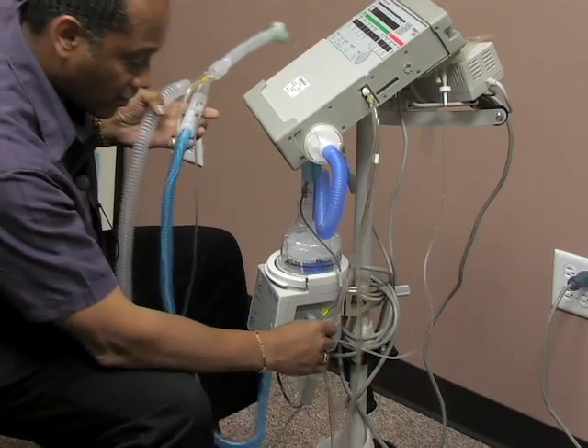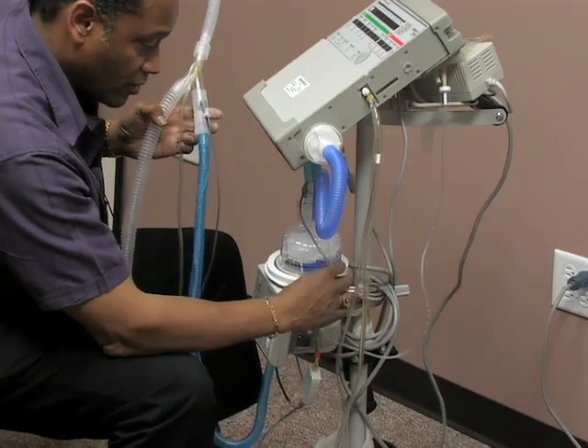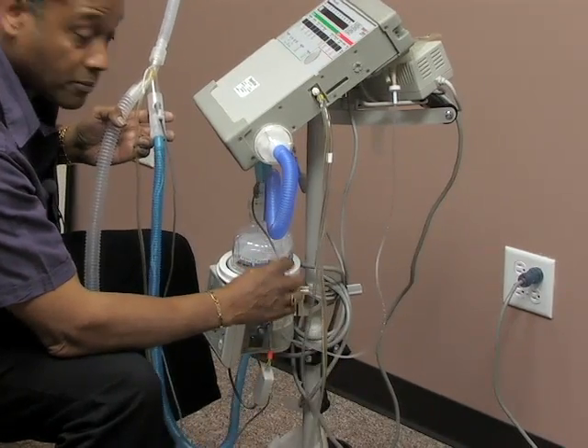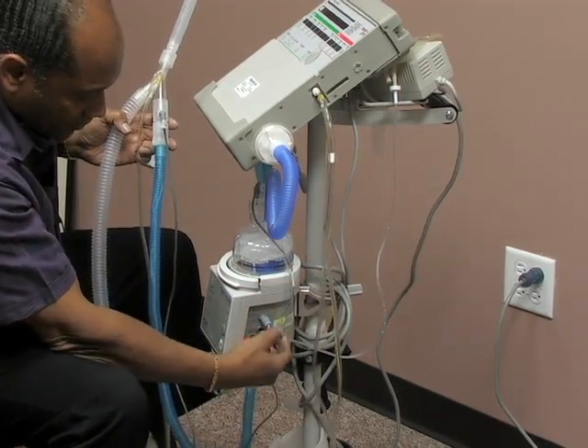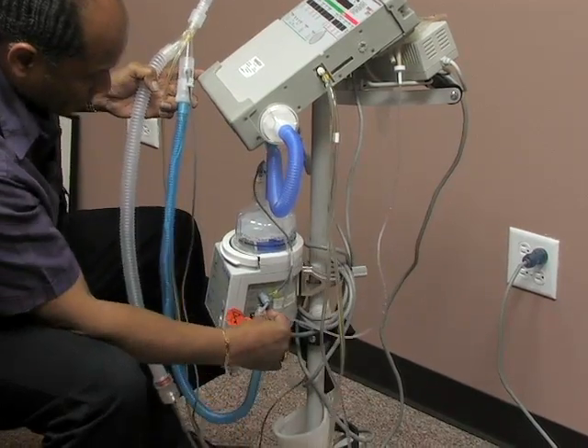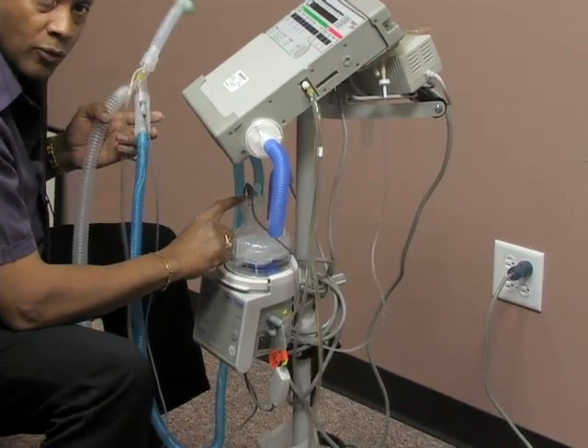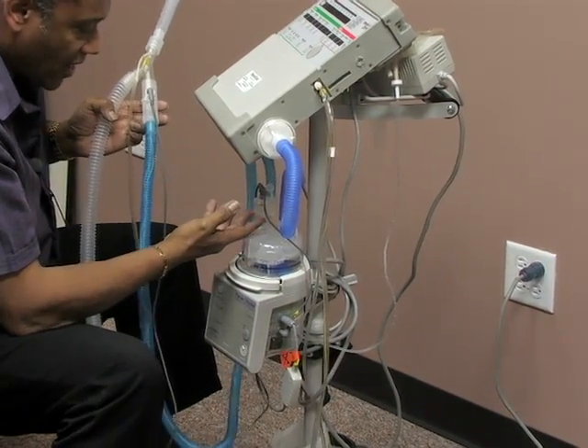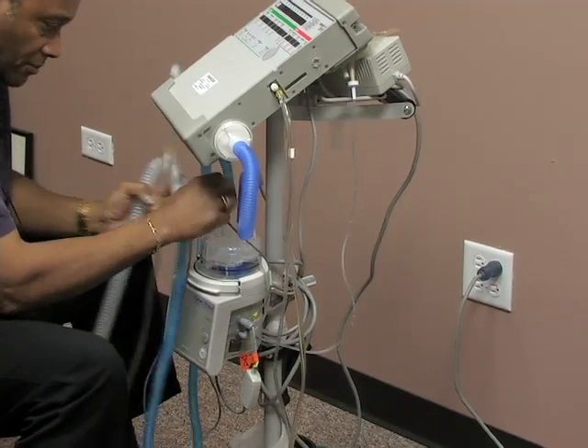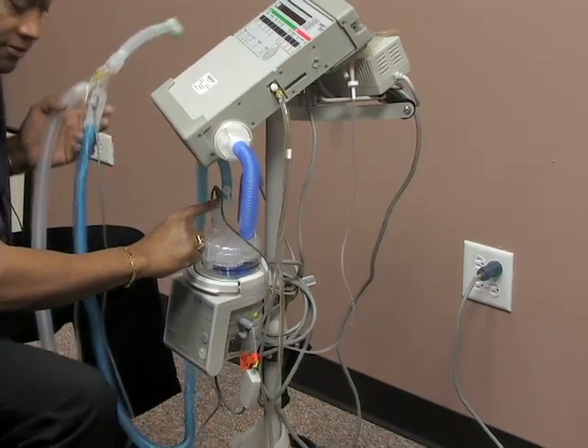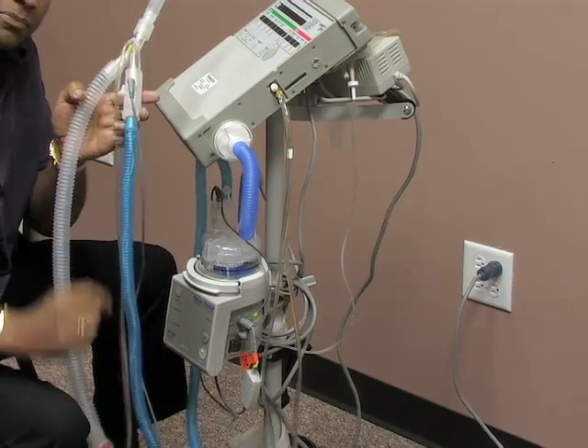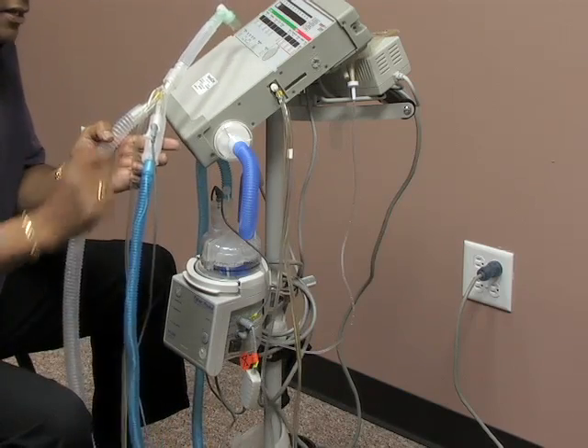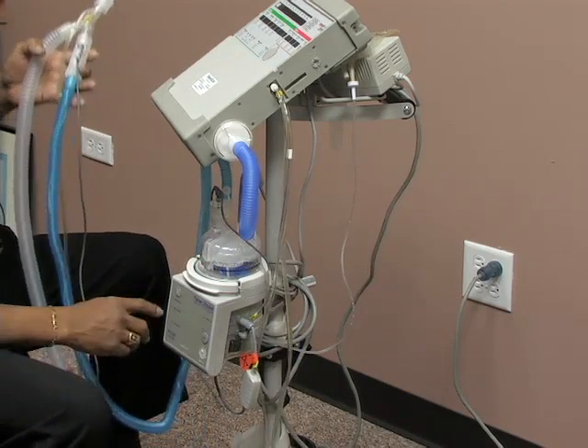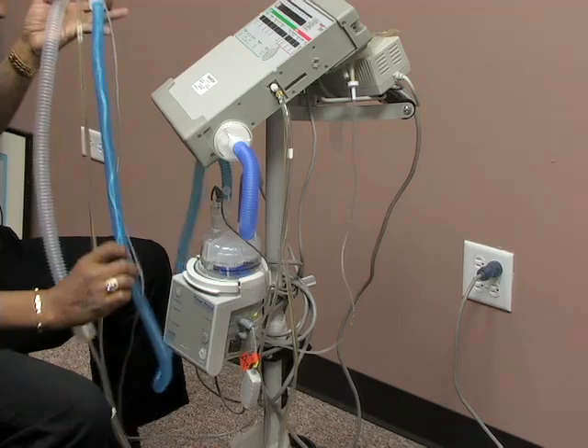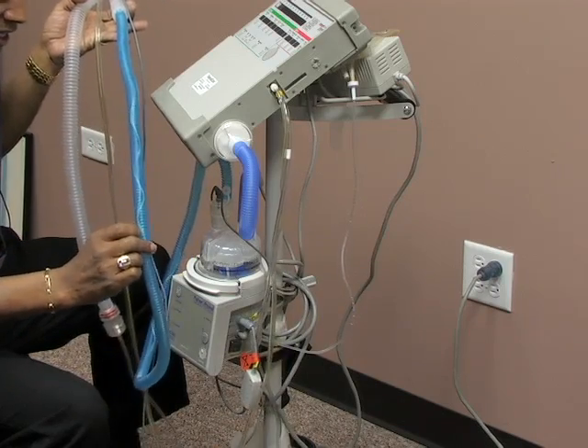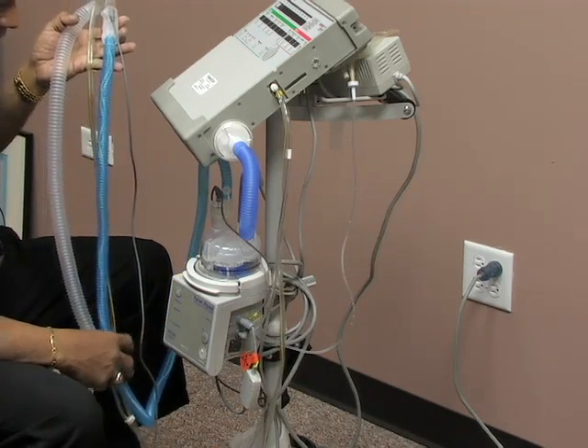Down here at the Fisher-Paykel are your thermocouple or your temperature probes. It plugs in here at the bottom port. And here, when the heated air, or humidified and heated air, initially comes out, there's a temperature probe here that measures the temperature. And then there's another one that measures the temperature just before it enters into your client's airway. This allows the Fisher-Paykel to better manage or control the heated wiring in here to keep the condensation out.